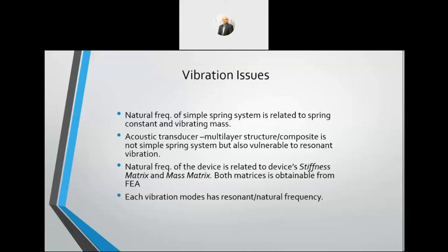So the natural frequency of the device is related to the device stiffness matrix and mass matrix. Both matrices are obtainable from a finite element analysis. This is why nowadays designers start their development cycle with finite element analysis, or so-called computer simulation, before proceeding into fabrication.